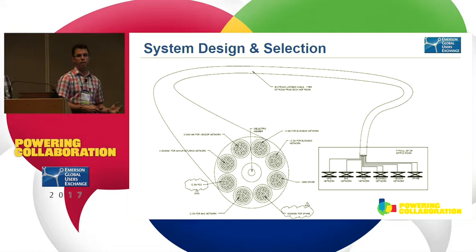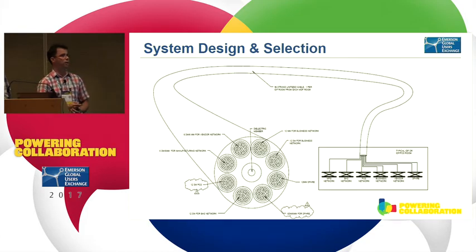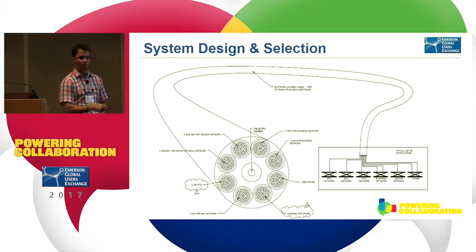So here is the diagram of what we call the unitized cable. This is the backbone cable that runs from every main distribution facility room, or MDF, to every intermediate distribution facility room, or IDF, where the servers are located and the switches as well. It contains 96 fiber optic strands, and from those 96 strands, we have a total of 16 fiber optic for our system.